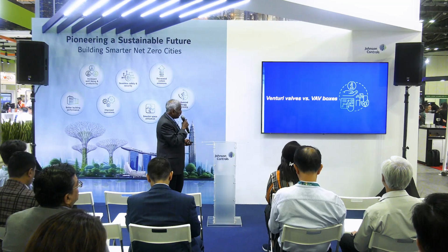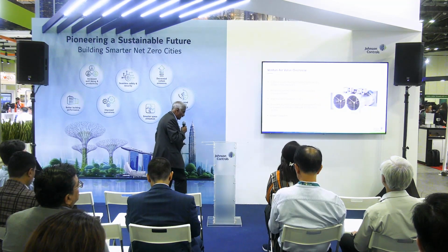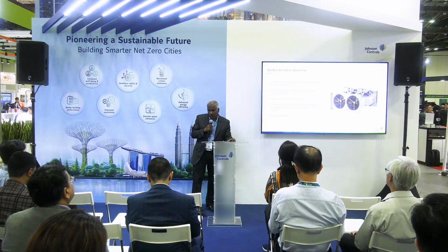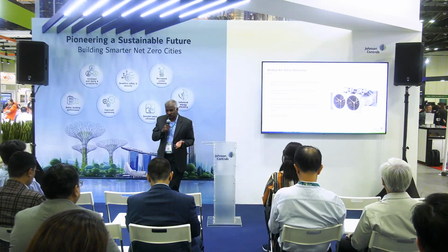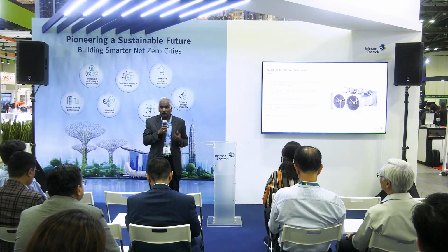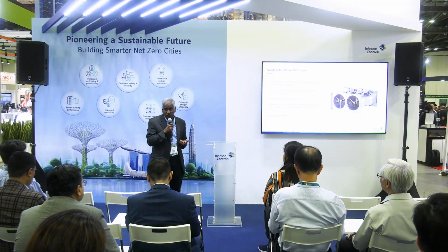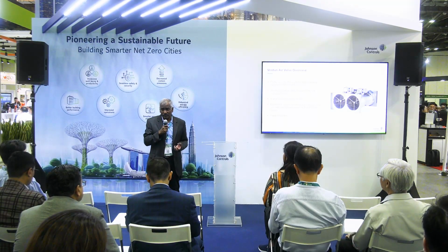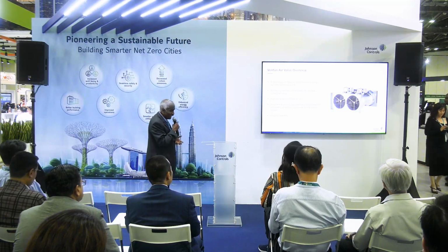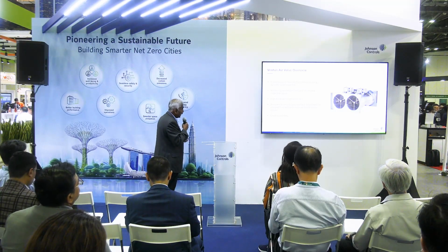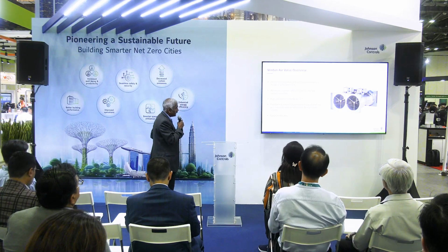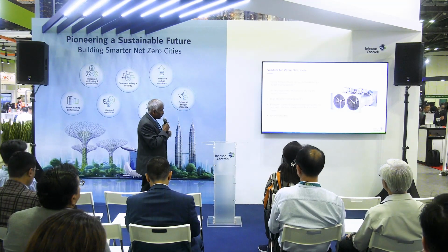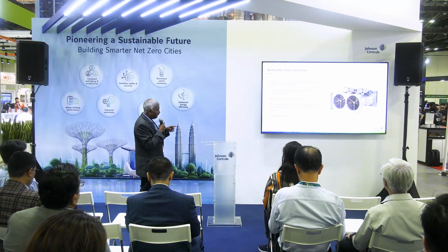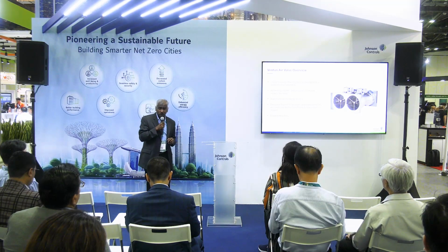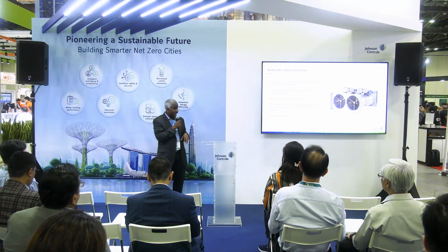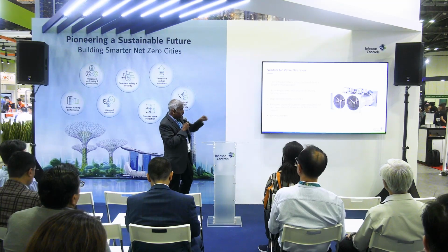So we're going to talk about why Venturi valve, because we have seen some sites where customers have asked for VAV boxes, but our Johnson Controls recommendation is always to go for Venturi because it's proven. That's what you should be using for environmental control, especially for OT and critical areas. It's a highly accurate flow metering device utilizing a dynamic cone assembly, as I've shown you earlier. It accurately controls airflow even at very low velocity pressure. Again, it's fully tested and fully calibrated, with a high turn down ratio of up to 20:1.